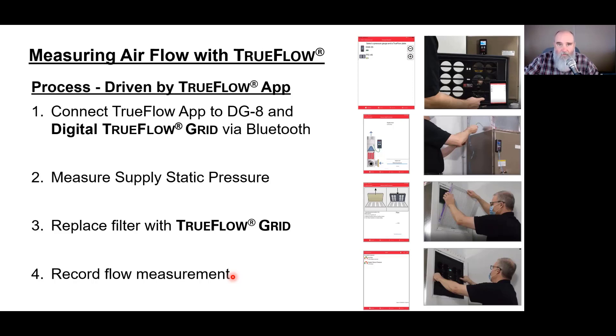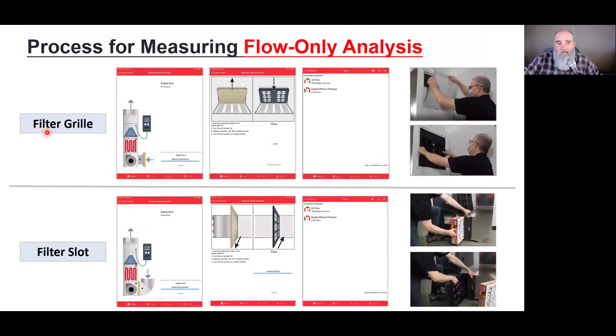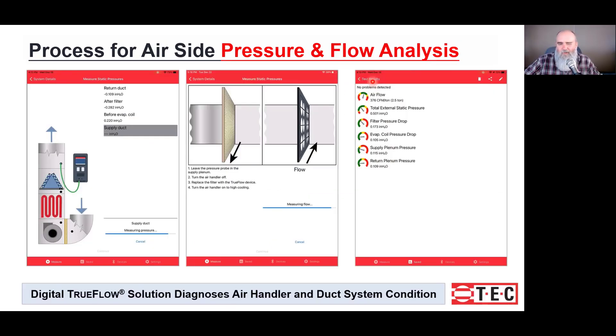Notice I said measurement of airflow, not estimate of airflow. We can see here in a filter grille application, the process is as described: measure your static pressure in the supply with the filter, remove the filter, insert the TrueFlow, and record. It's also shown here in a filter slot application.